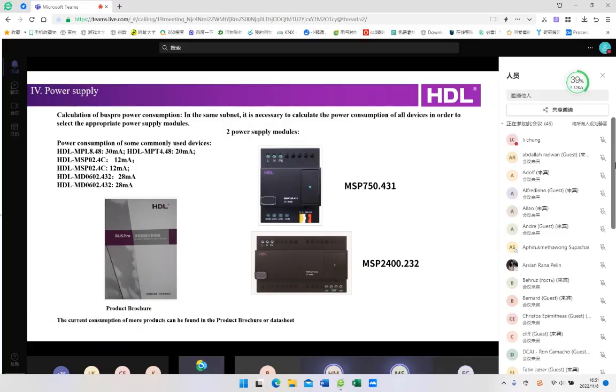For example, if you want all of these devices in your system, you can refer to the brochure or data sheet, find their amperes, and add them together. But guys, please note, this is very important: the total consumption of the devices in the subnet shall not exceed 70% of the power supply.